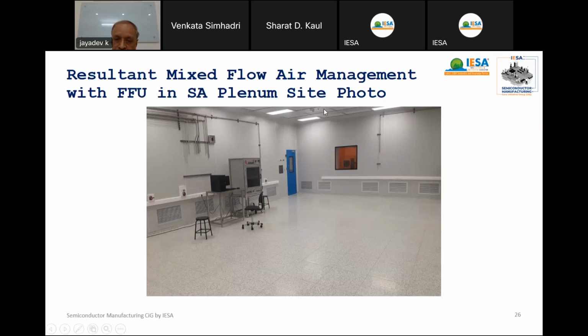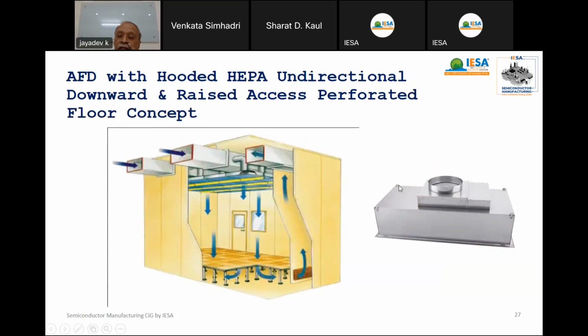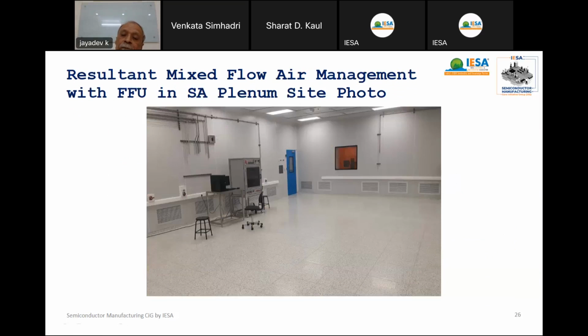Air comes from the filters, goes all along the return path, and comes back. You can see all along the return air path we have grills with return risers to control temperature and humidity. This return air is more important. Some part of the air from the room is taken back to the AHU to control temperature and RH.